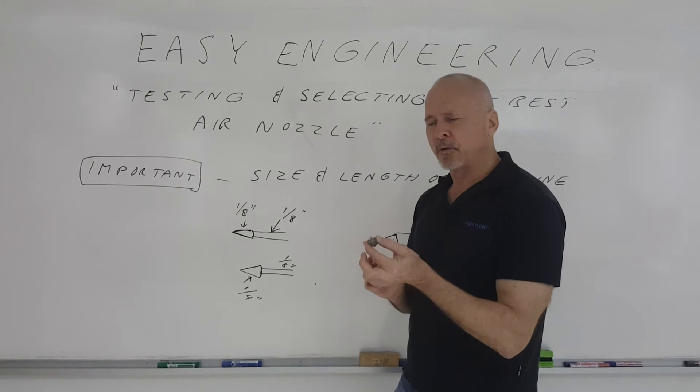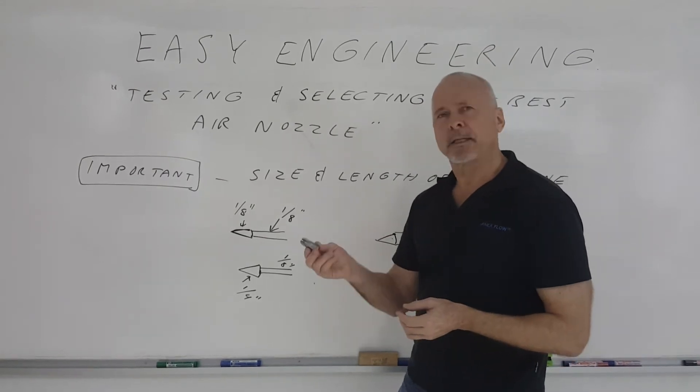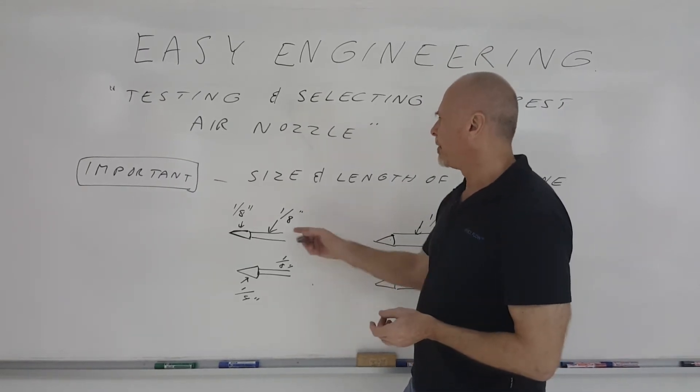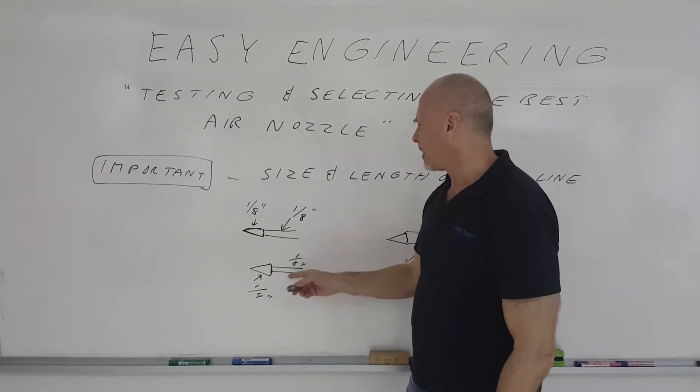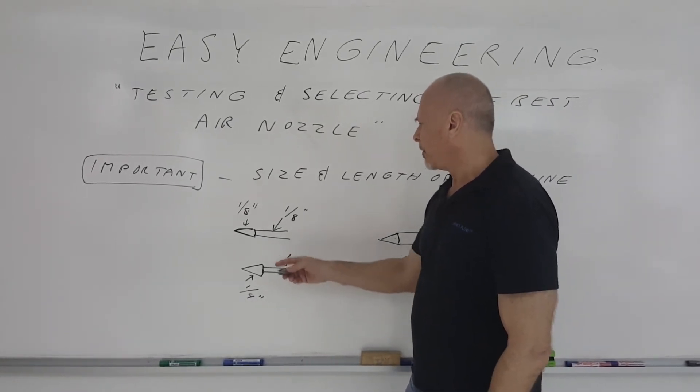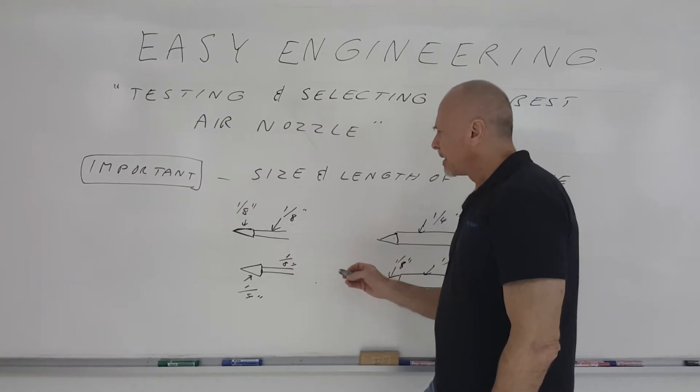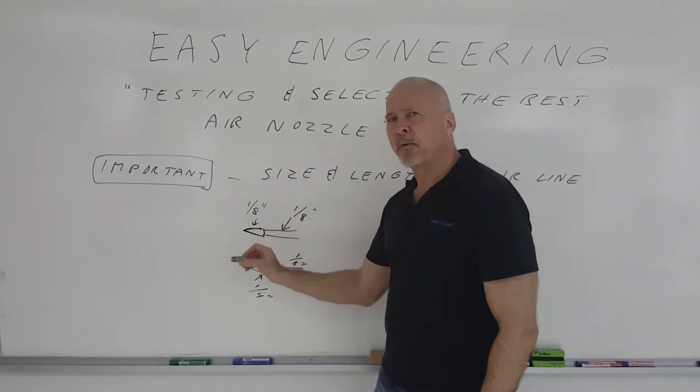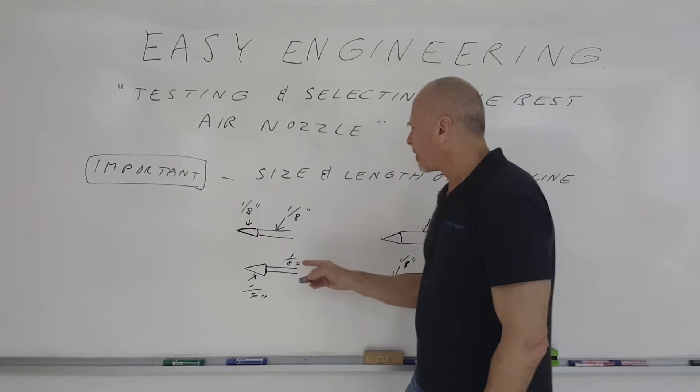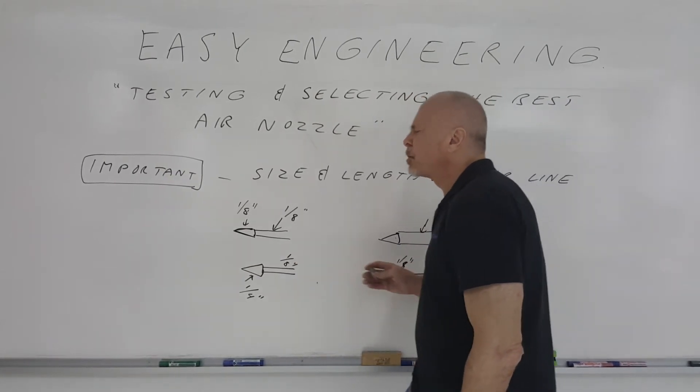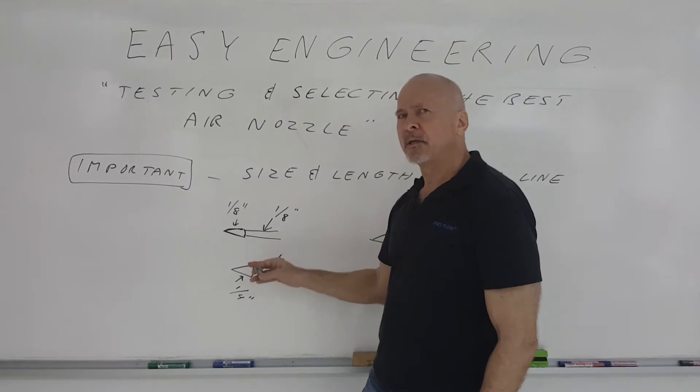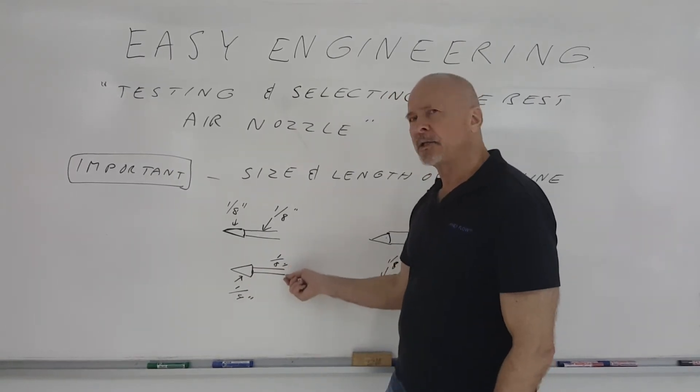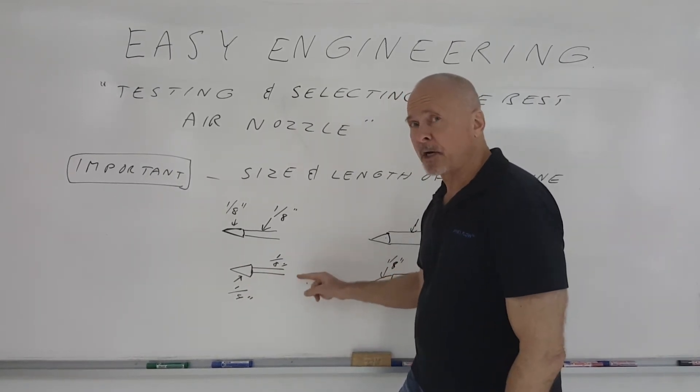So you get the quarter-inch nozzle and the one-eighth inch nozzle and hook them up to your one-eighth inch line. When you test the quarter-inch nozzle on the one-eighth inch line, you're only going to get a certain amount of force going through that nozzle because the one-eighth inch line is trying to force through the flow that the nozzle needs. But because it's a one-eighth inch line, you're going to have a lot of pressure drop in that line.